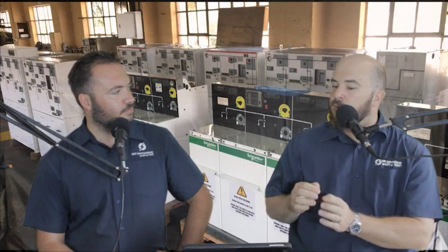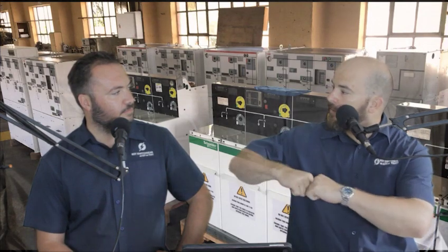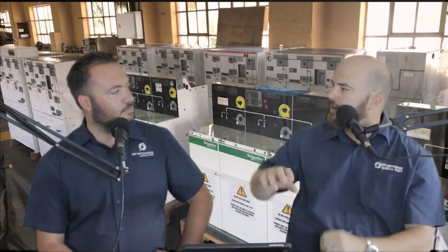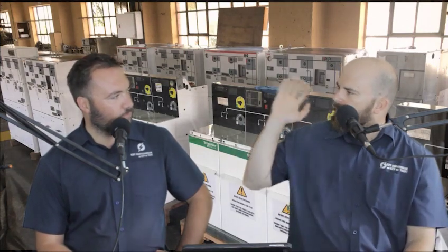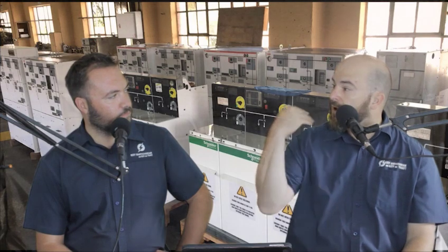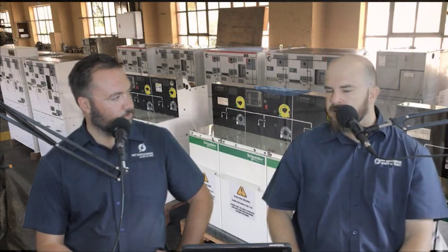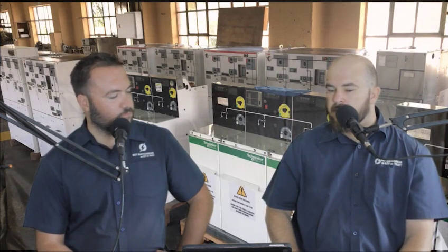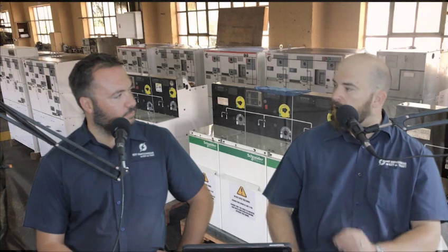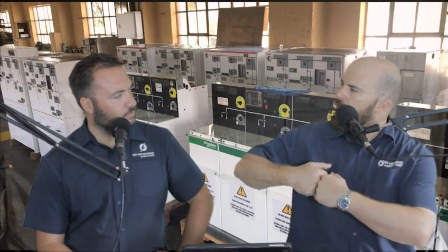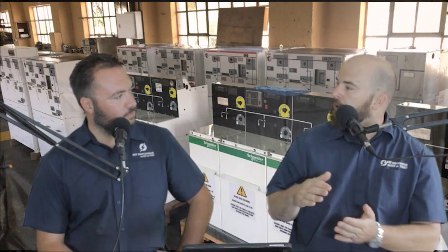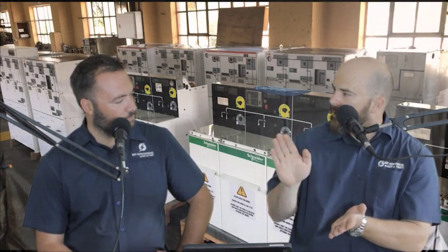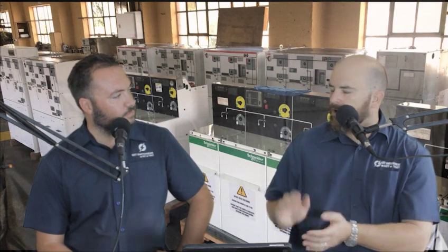It's not just that when there's a fault current you remove two contacts from each other. There's something we call an arc, which is like a big flash, almost like lightning, which we will cover extensively in one of the next topics. But for the sake of this, a circuit breaker is the only one that can actually open and manage that arc, whereas the other ones can operate in nominal currents, but not in fault currents.